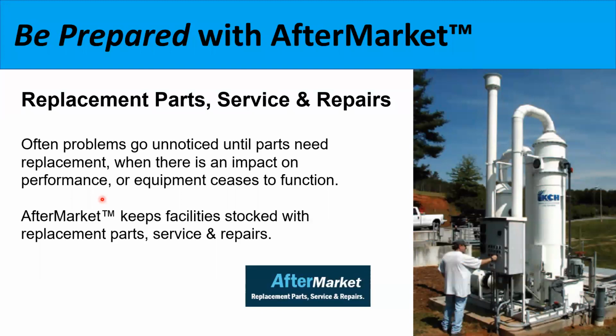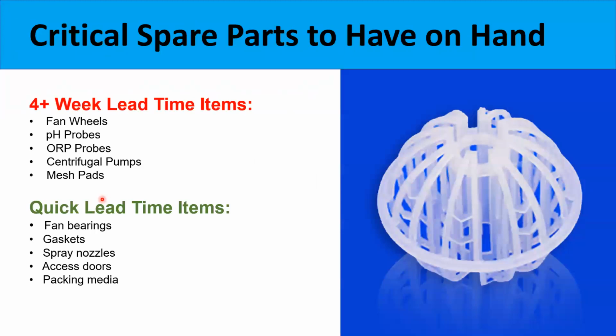And then certainly we recommend replacement parts to keep on hand. The critical parts to keep on hand are oftentimes pH probes, an extra pump, maybe an extra fan wheel and shaft, and composite mesh pads, and some others, fan bearings, gaskets, spray nozzles, access doors, and possibly some packing media. As you can see here, the lead time on some of these items at the top is 4 or more weeks, so it'd be very good to keep those on hand so that in case something really fails in a major way, you can pull it right off the shelf. And things that are typically quicker are those spray nozzles and bearings. We do highly recommend, though, keeping an extra set of fan bearings on your shelf to reduce downtime.